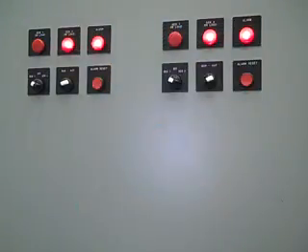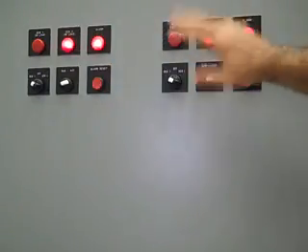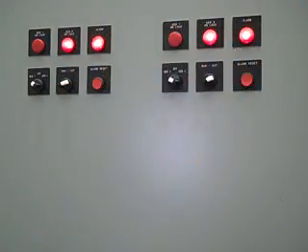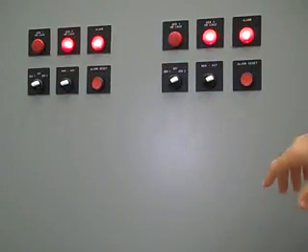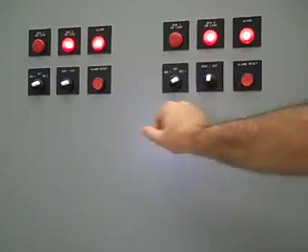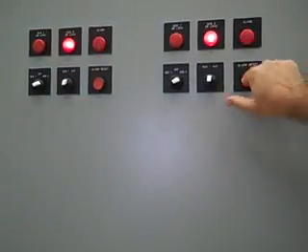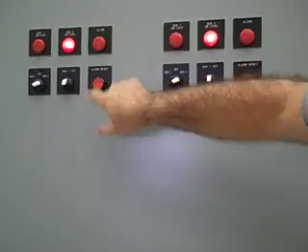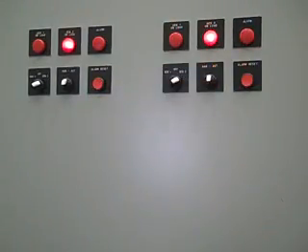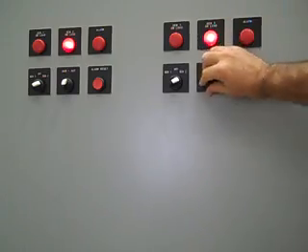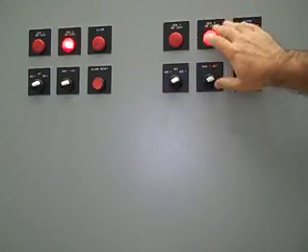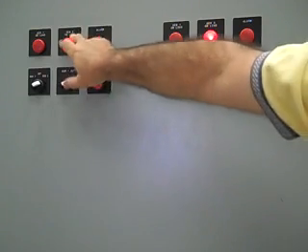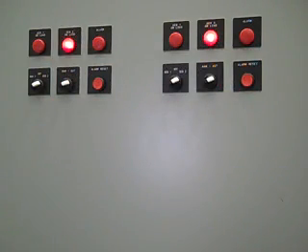we got the transfer switch transfer to generator 2 and generator 3. But now what we're going to do is put it in manual, reset it, so the 2 faults are gone. And once I flip to auto again after I reset, what's going to happen is it will keep running on generator 2 and generator 3.